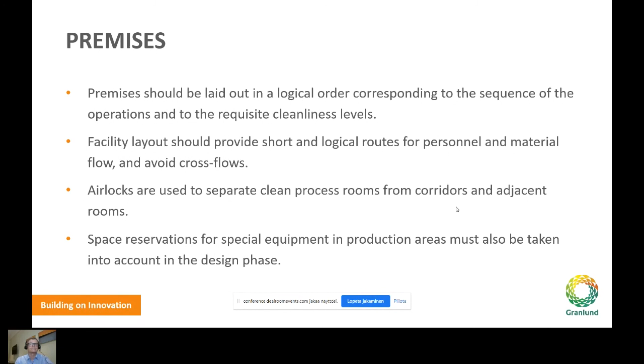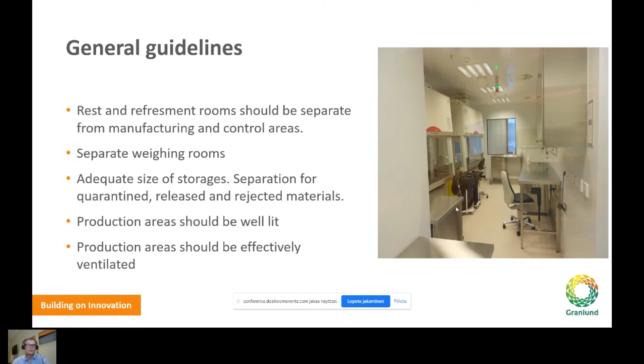Some points from general guidelines: rest and refreshment rooms should be separate from manufacturing and control areas. Sometimes toilets are put in the first corridor, but it's perhaps better to put them totally outside the clean room area. There should be separate weighing rooms, good-sized storages, and separation for quarantined, released, and rejected materials. All production areas should be well lit and effectively ventilated.